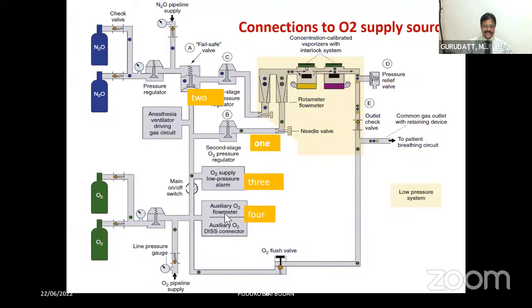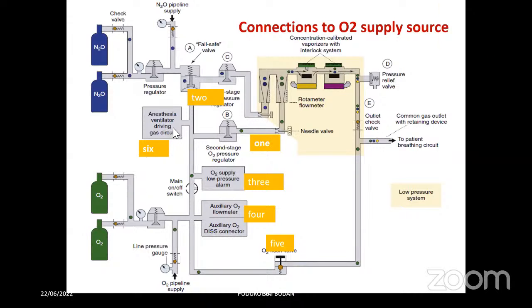Then again, auxiliary oxygen flow meters. This is not present in every workstation. In advanced workstations like Aisys CS2, we do have auxiliary oxygen flow meters. This can be used even when you are not operating the master switch, and directly you can provide supplementary oxygen to the patient. So this is again an oxygen connection. That is the 4th connection. The 5th connection is to the oxygen flush, and the 6th connection, in case of GE machines, is to the ventilator as a driving gas.